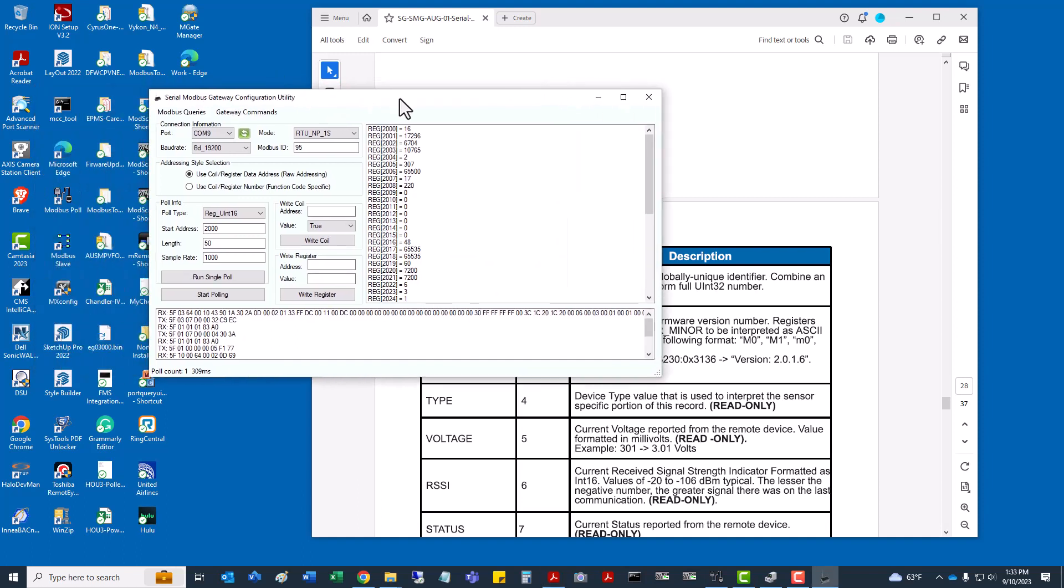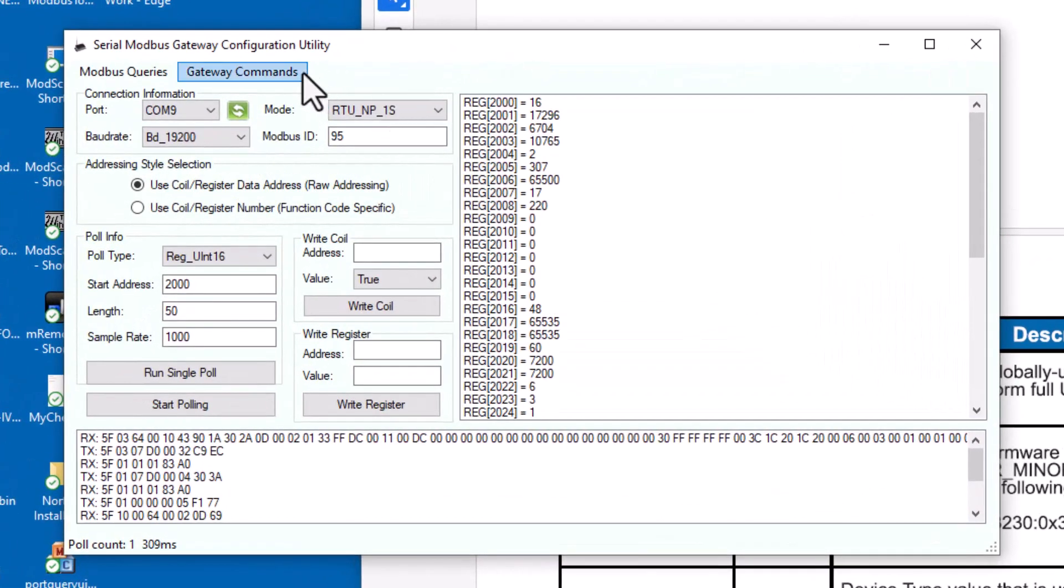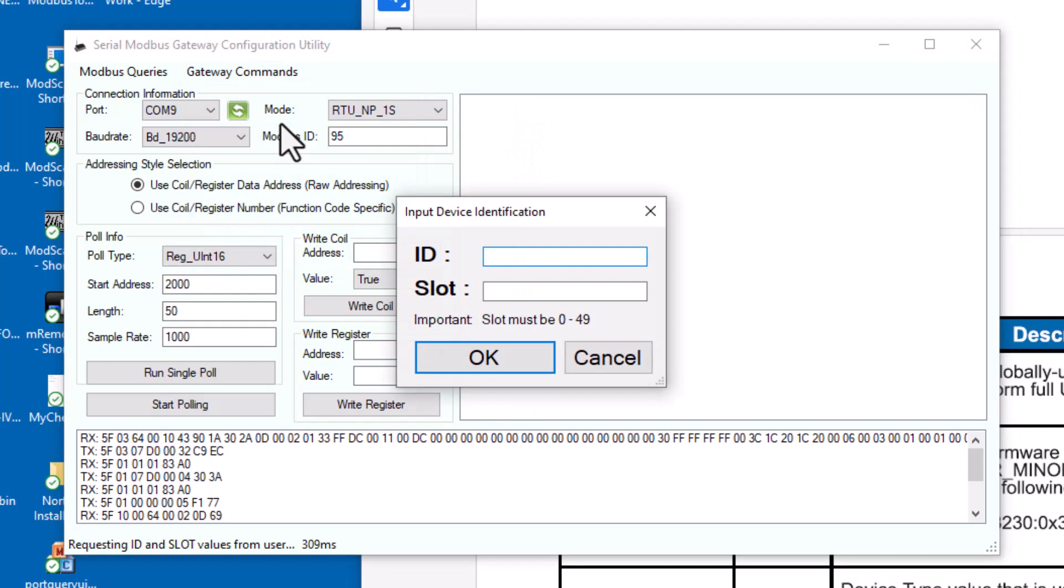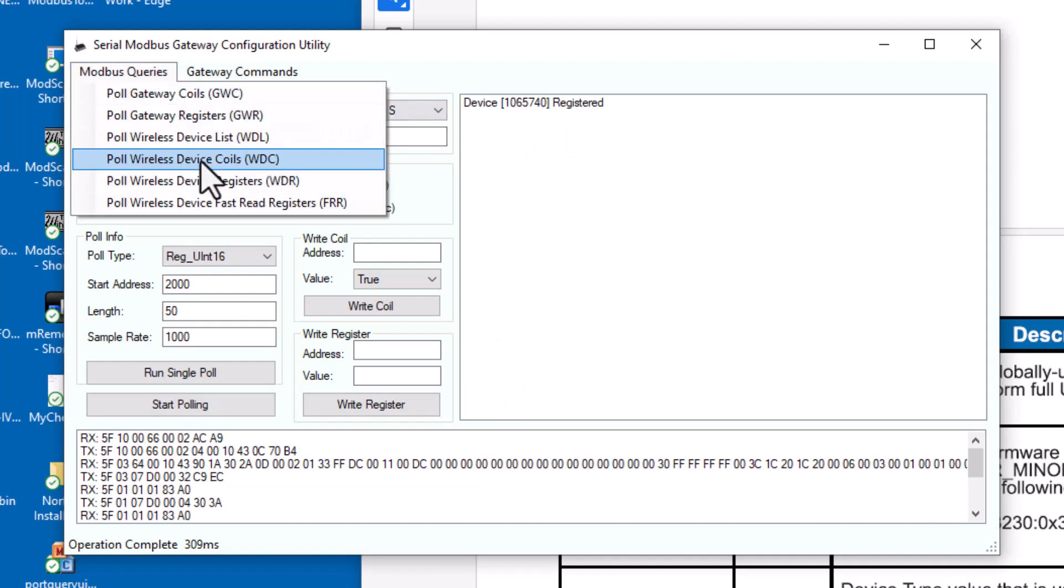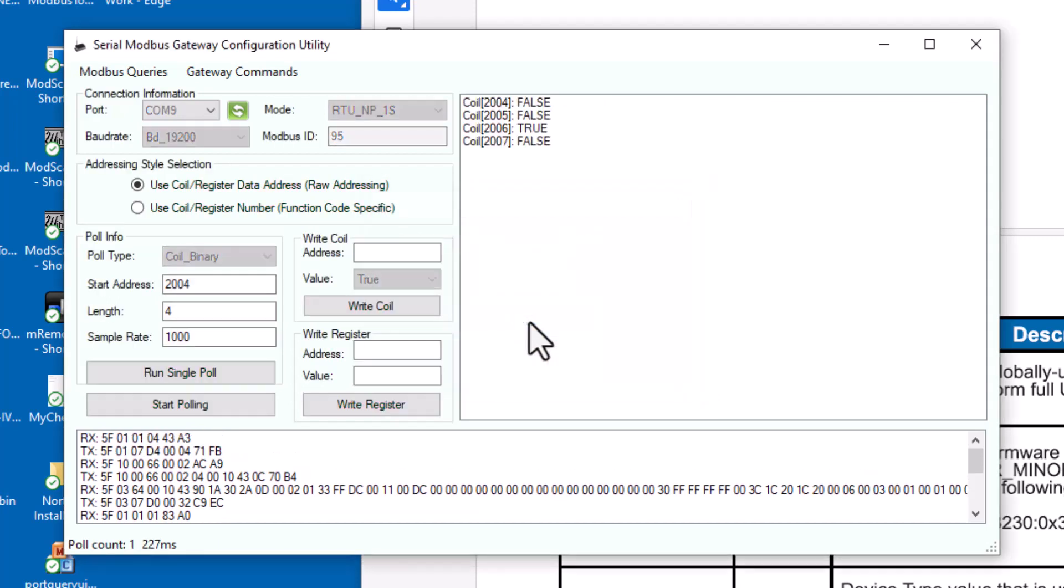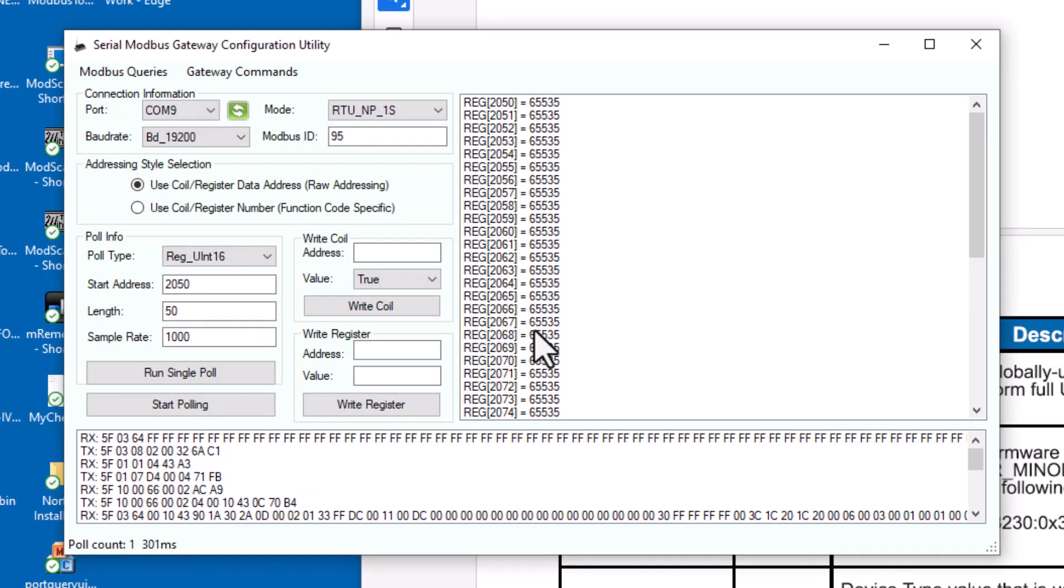It looks to be a lot of different options depending on the sensor type that you're using. I'm going to go through and do my second sensor just to make sure that the process is repeatable. On the second one, I have a humidity sensor. I'm going to go to Gateway Commands, Register Wireless Device. The ID on this one is 1065740. We'll put this one in the second slot, click on OK. It shows the device is registered. Now we should be able to go Device Coils, go to that second slot.